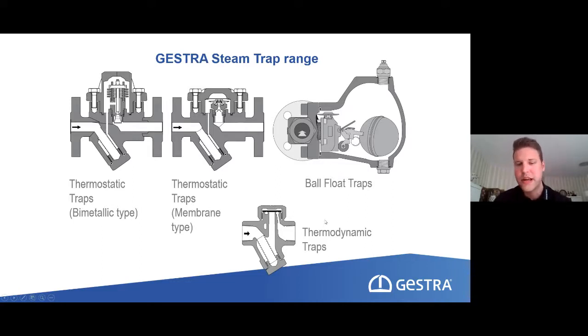Then we have another one, the thermodynamic steam trap, which is, I would say, the most common steam trap in the world. Around 50% of all steam traps in the world are thermodynamic traps. It depends a little bit on which country we are in. This has one very simple reason: thermodynamic traps are the cheapest ones. But when we think about these kinds of steam traps, we have to consider the two basic requirements, the loss of live steam, which was the first one, and the automatic air venting. We might get problems with such a design. So this kind of steam trap is only suitable where steam doesn't really have a price. But as soon as steam has a certain price, then we should not think of this kind of steam trap.